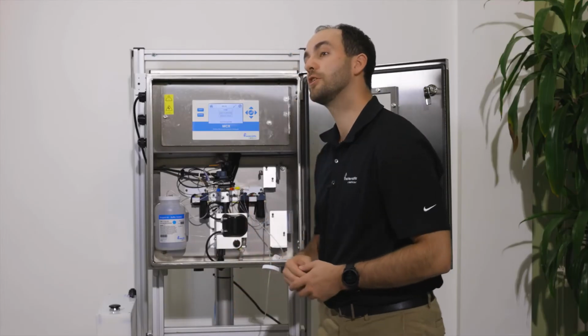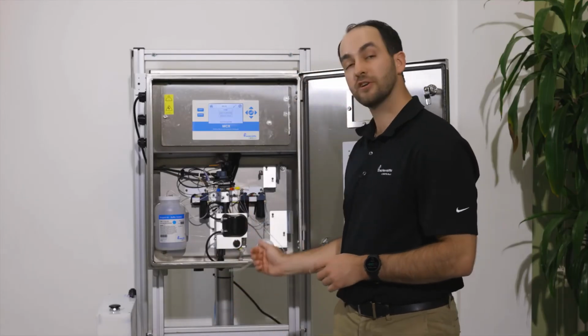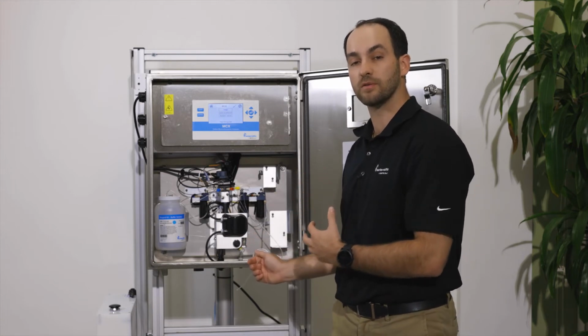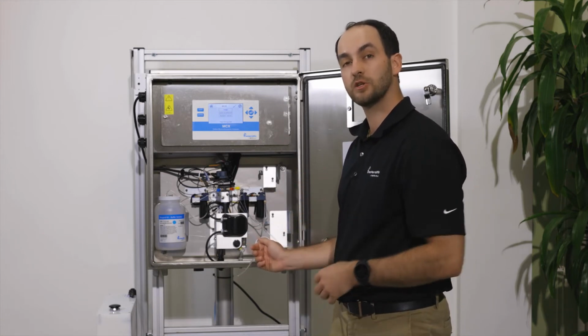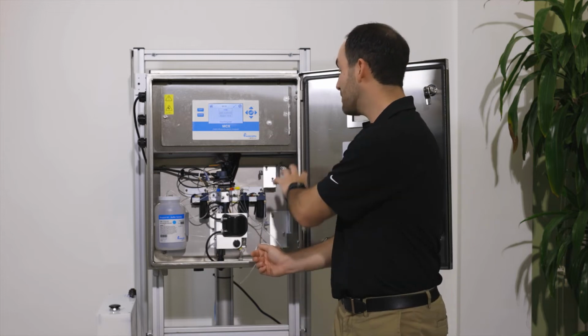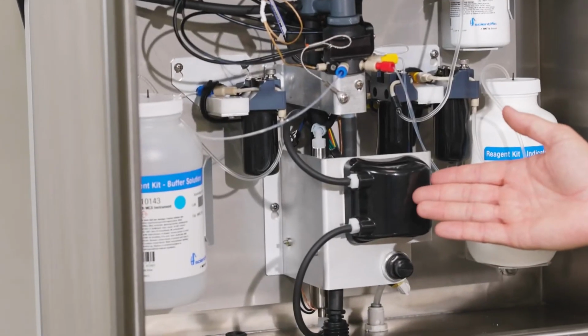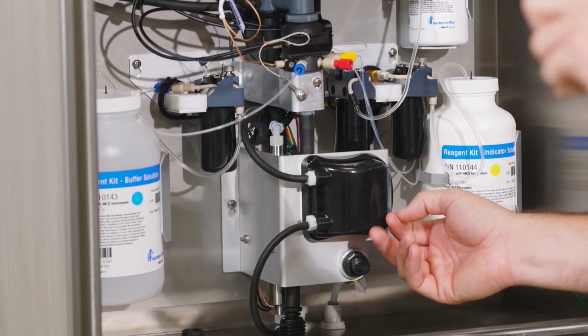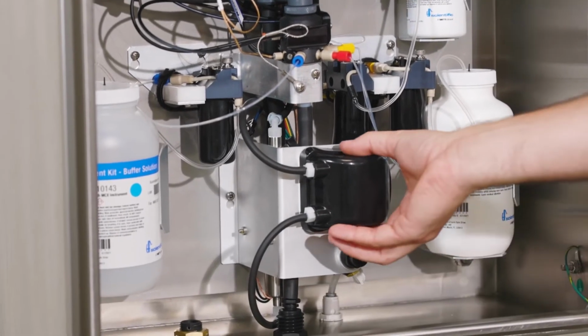After you've completed putting your new pump in, we want to make sure we flush the reagent lines that you've taken out of the bottles. Once you have flushed the reagent lines, you will need to perform a prime on any bottles that you have taken out. To change the peristaltic pump, start by pressing your fingers on the top and the bottom to pull the pump off.